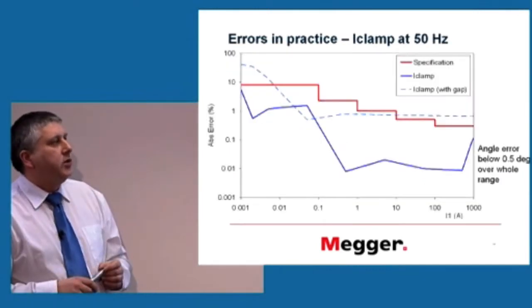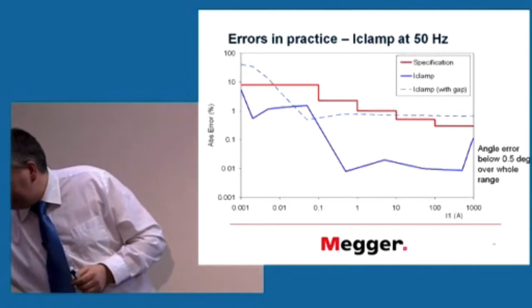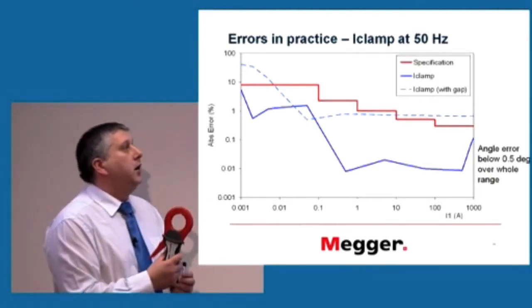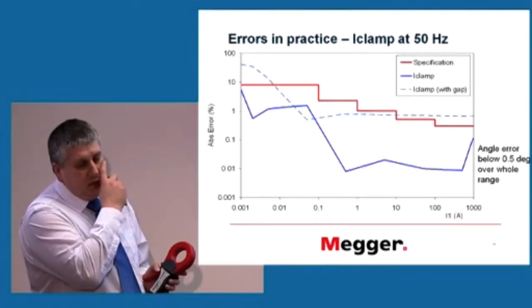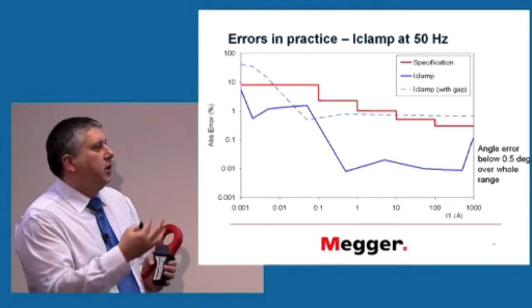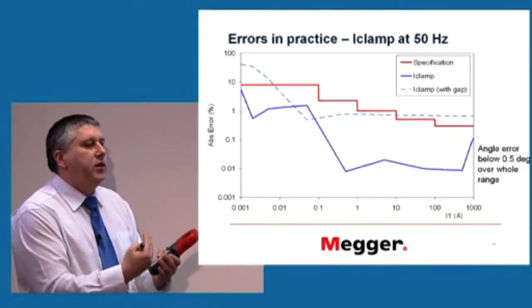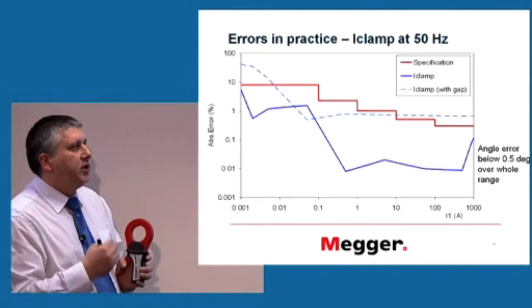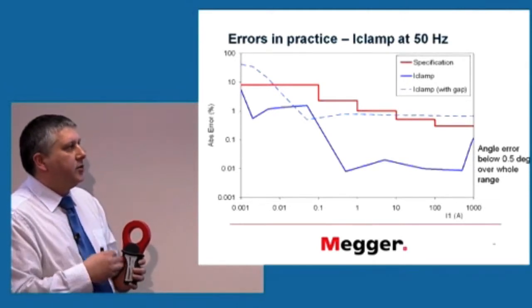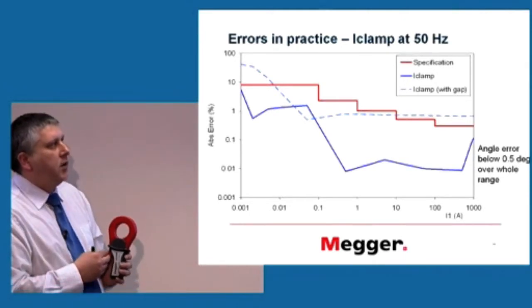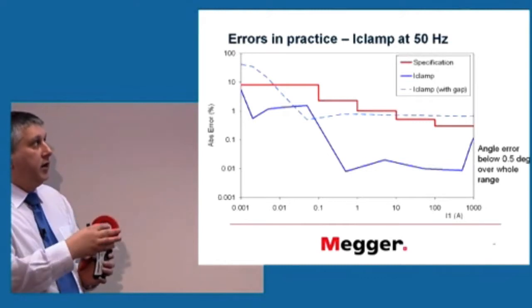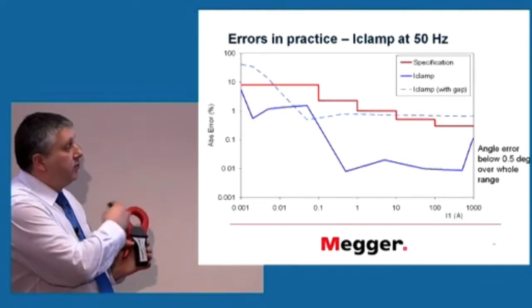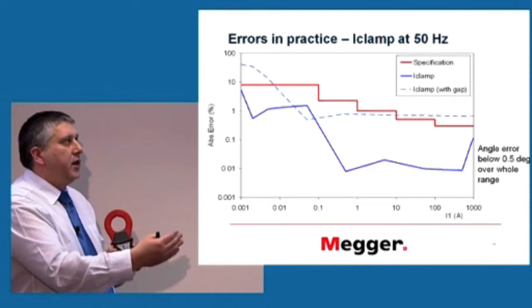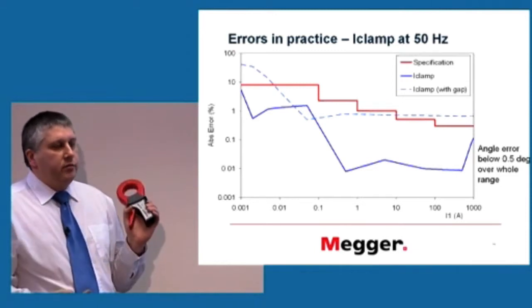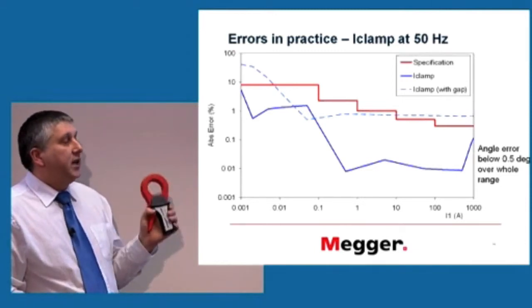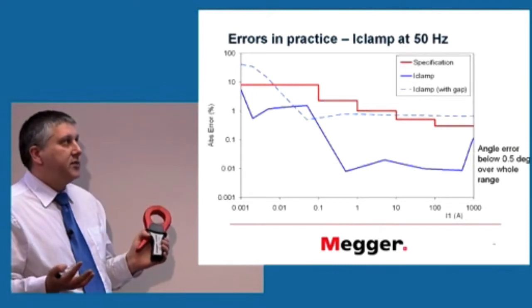Just to show you some errors in practice, if we take this device, the red line you see there is the specification for it. Obviously, the lower the current, the more difficult it is to keep very tight accuracy. But for high currents, we have 0.3%. And the solid blue line we can see that over the full range from 1 milliamp to 1,000 amps, the measured error of this current transformer stays below the red line, which is within specification.